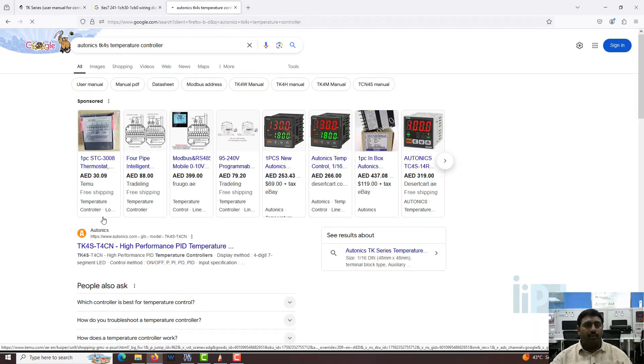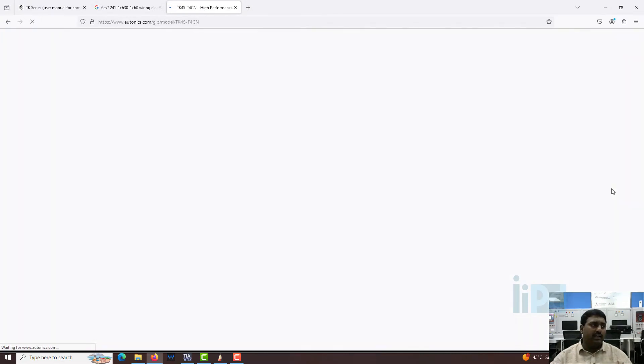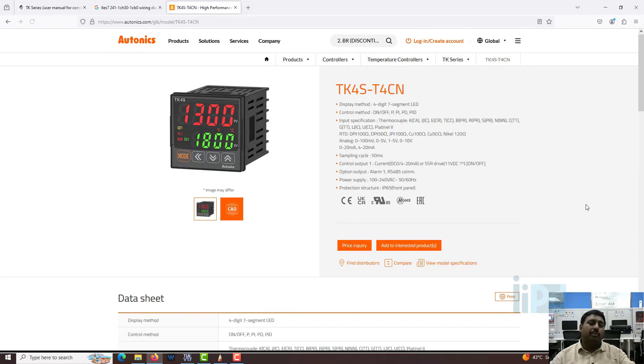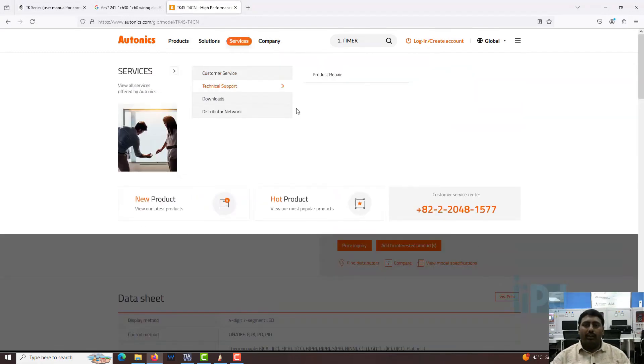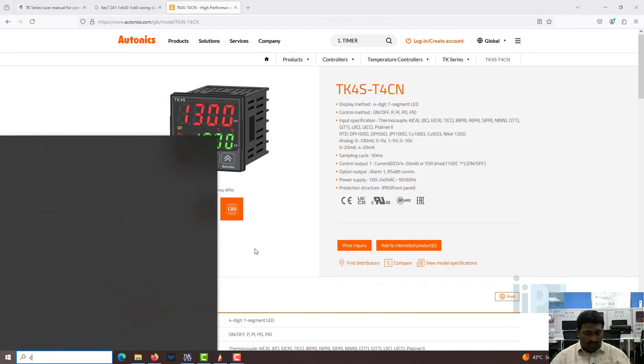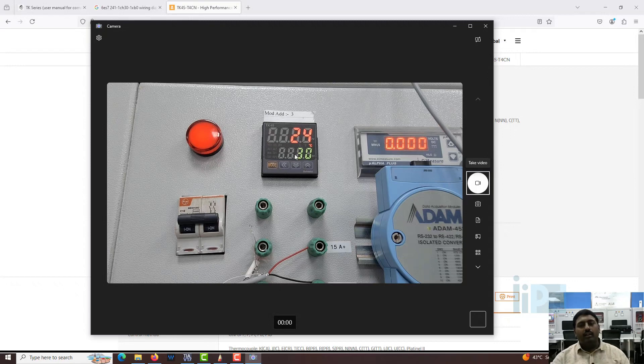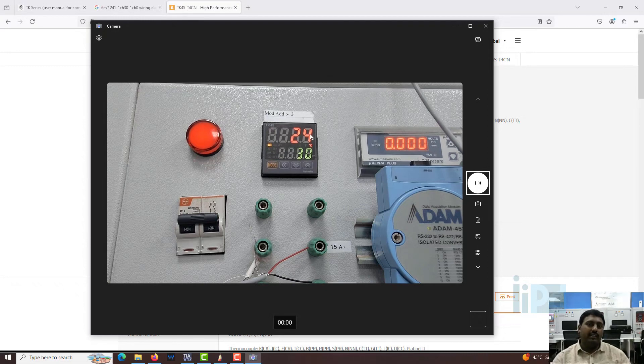The TK4S is a standalone PID controller that also has a communication function in particular models. We are going to read the current temperature and also set the temperature to the device. Let me show you the device - this is the TK4S with Modbus communication. The plus and minus terminals connect to the PLC. The current temperature is 24 and the set point is 30 - this is what we are going to change with our system.